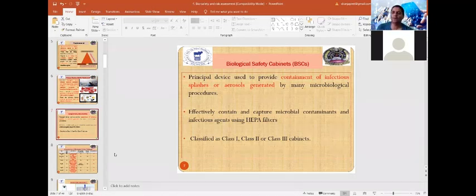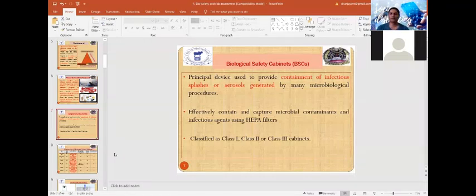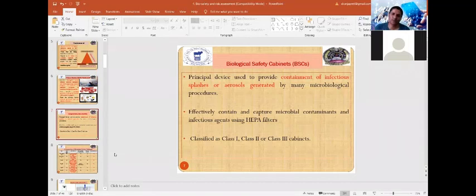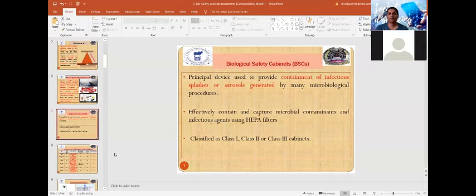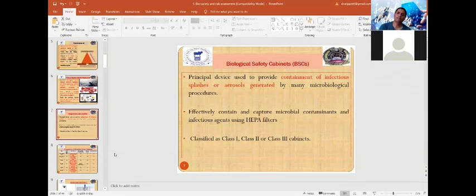HEPA stands for High Efficiency Particulate Air, and ULPA stands for Ultra Low Penetration Air. HEPA has the capacity to capture at least 99.97% of organisms with a diameter of less than 0.3 microns, while ULPA can capture microorganisms up to 99.99% efficiency for particles with a diameter of about 0.12 micrometers or more.